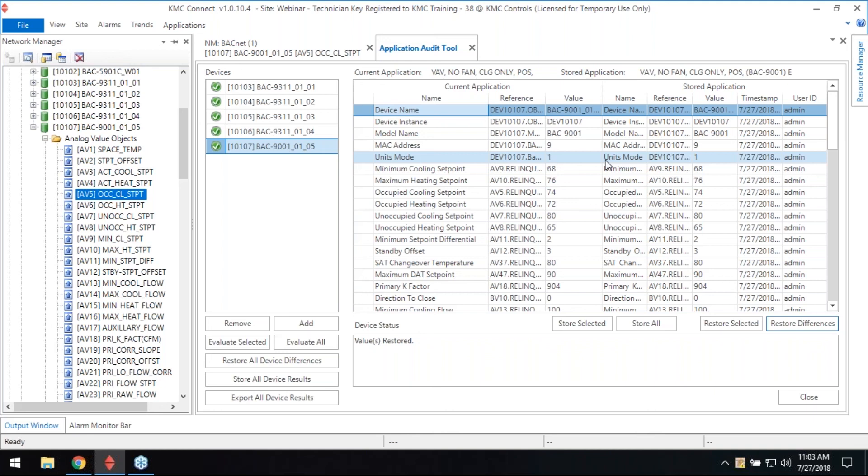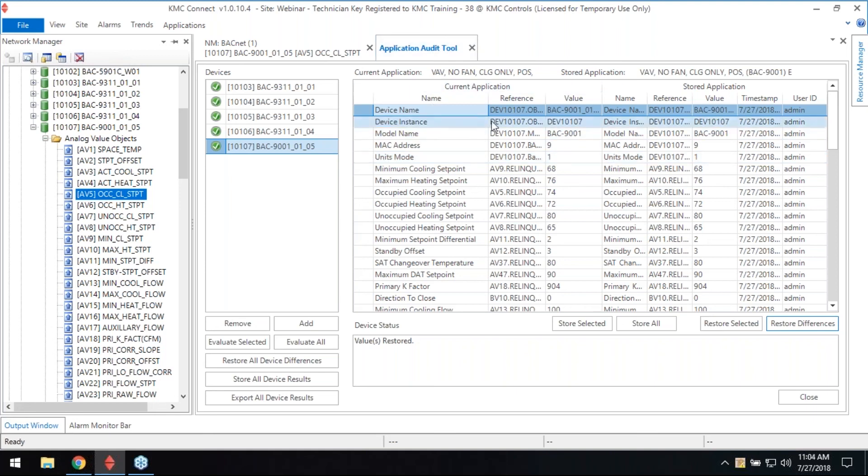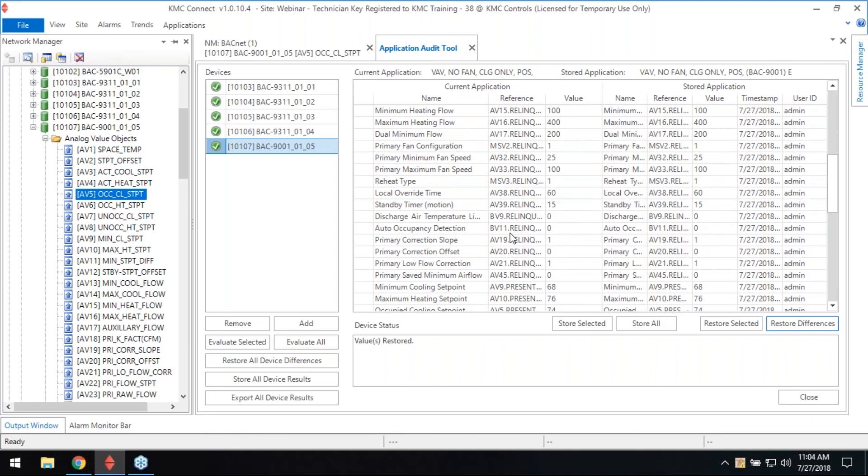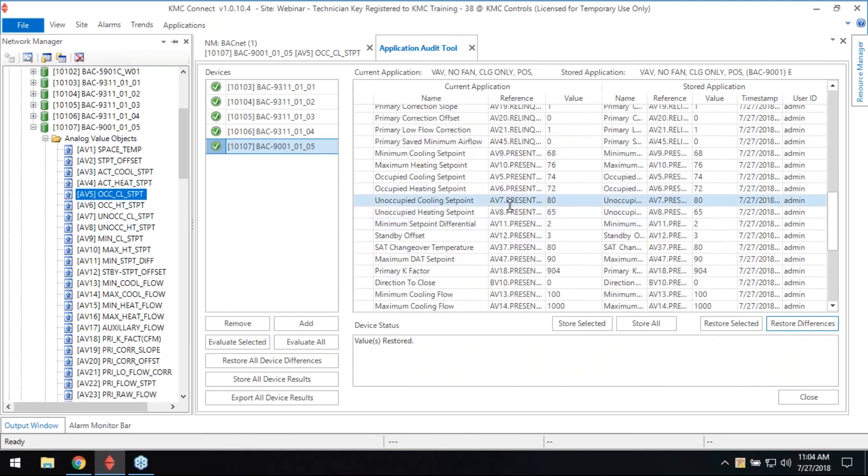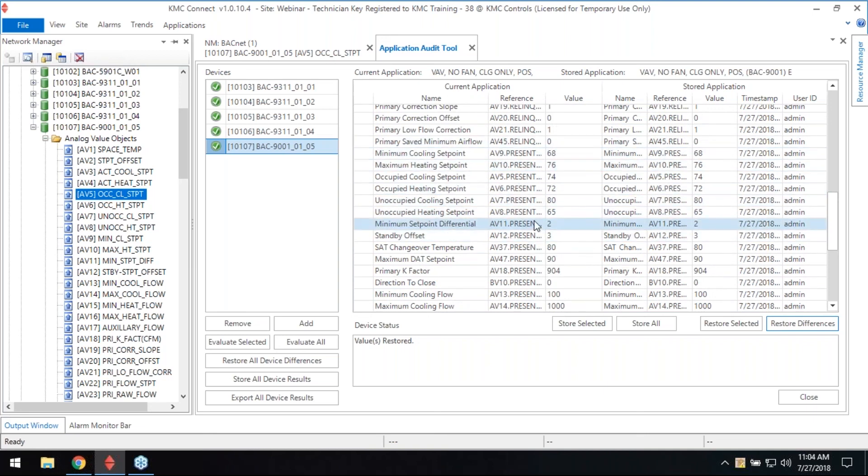I will entertain questions. I know we're running out of time. That was great. I do have a couple questions here for you. So the audit will not detect program modifications, but just looks at the values that the template designates as configurable. Is that true? Correct. It's a little bit more than the template because we also evaluate the coefficients like after balancing. So the balancer puts in the min max flows, things like that we think are important. Its name, you can see the device instance and its name and MAC address. The MAC address is not in the deployment tool. So there are a few more things in here than on page two of the deployment tool. And we're looking at the present value and the relinquished default value to help you decide whether it's an override or not.